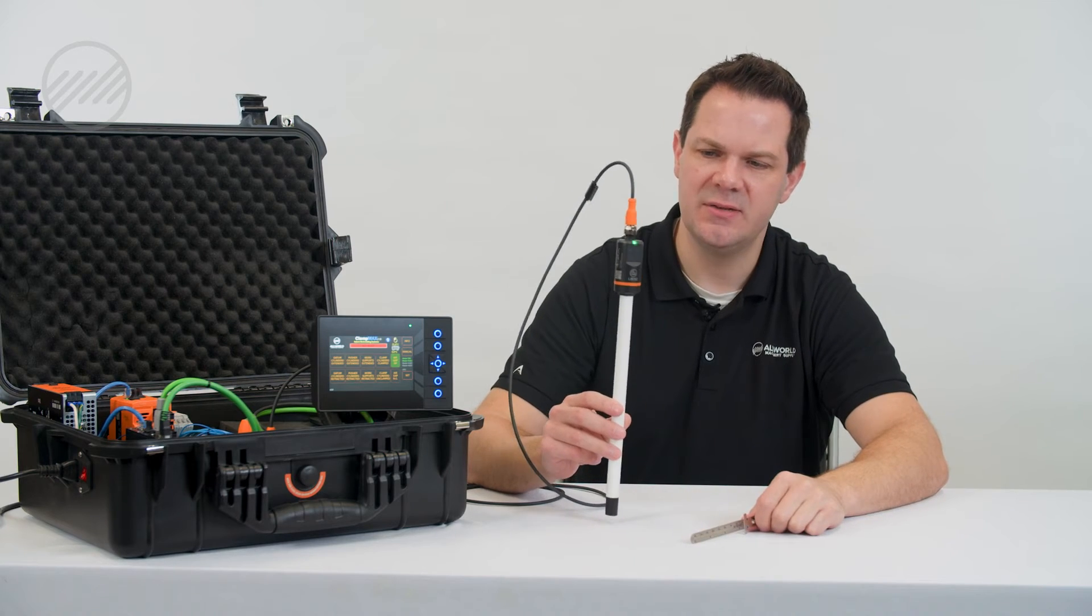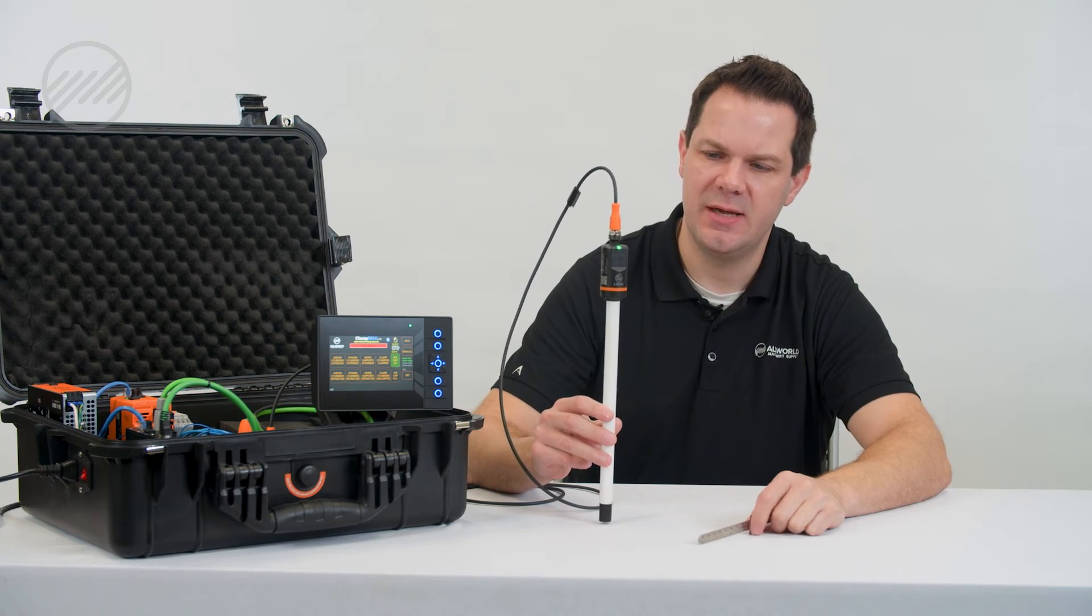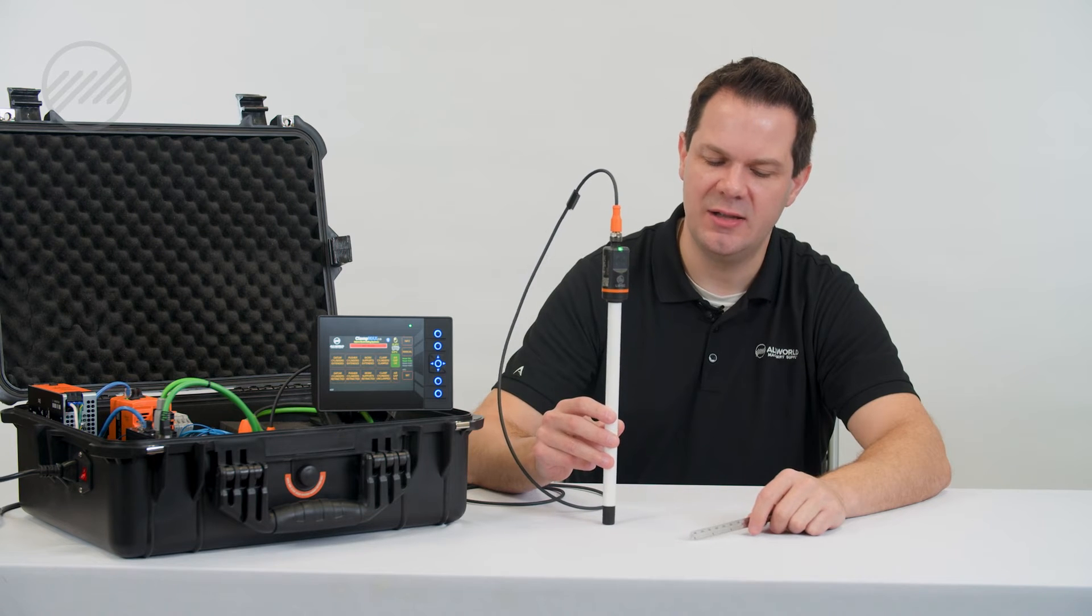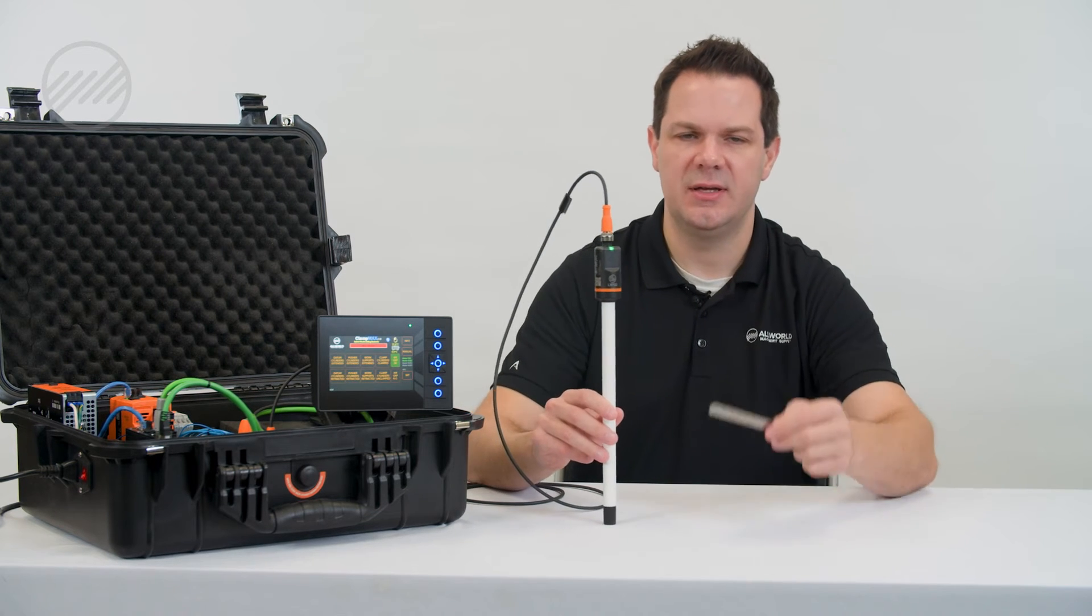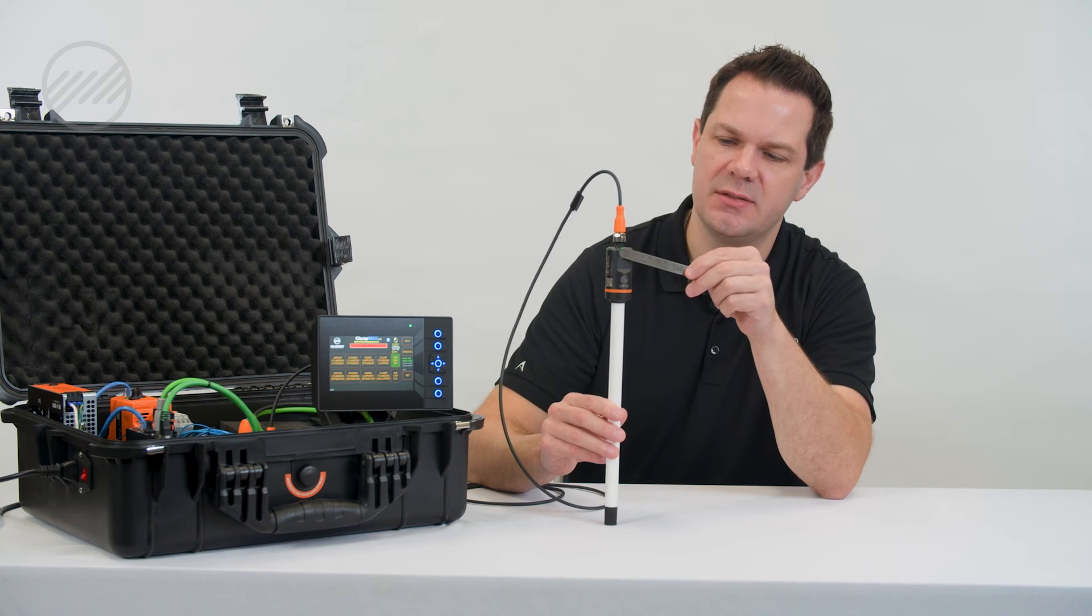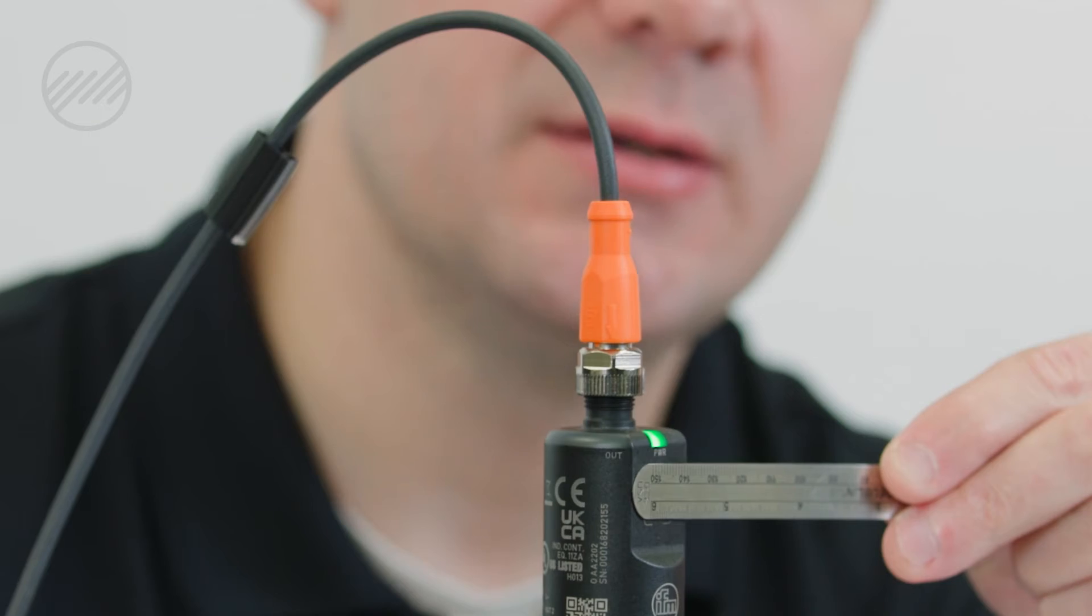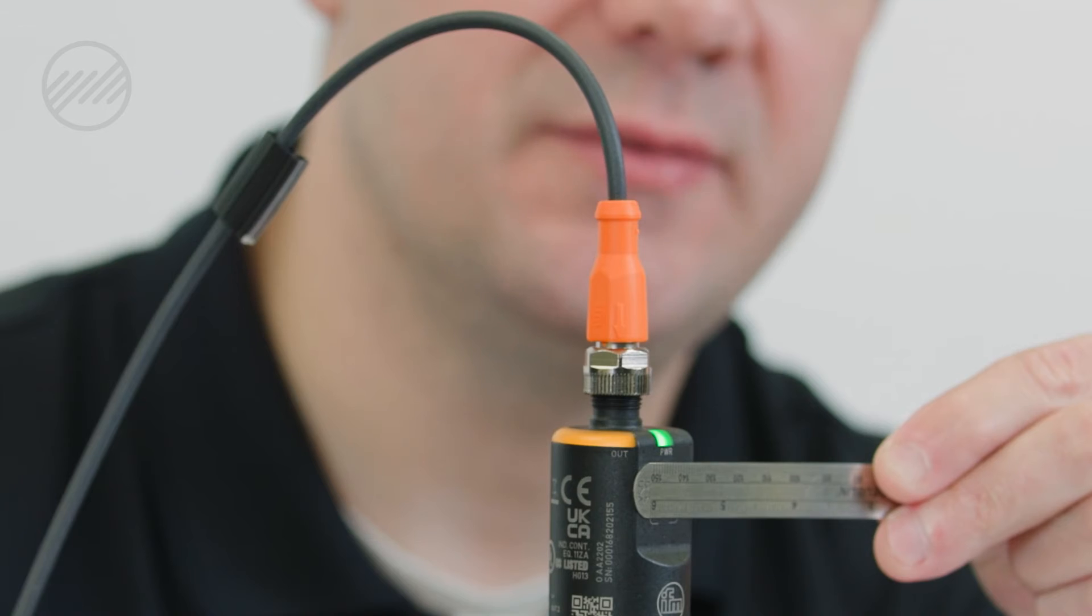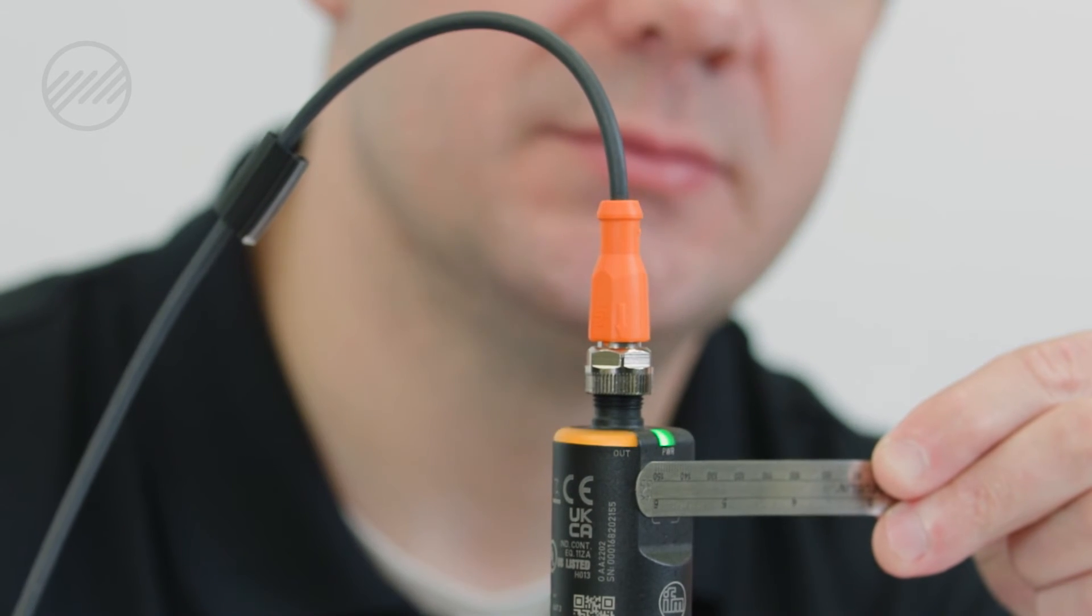Now we can fill our tank and we can teach it our full or high level or low level. You do that again by taking your metal object, holding it over the face. It'll flash three slow times for low level, three fast times for high level.